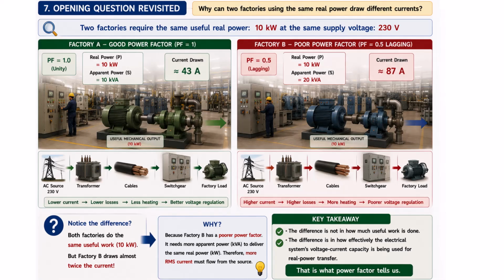Now return to the mystery from the beginning. Two factories require the same useful real power. Why can one factory draw much more current than the other? Because the factory with poor power factor requires a larger apparent power for the same real power demand. Therefore, its source, transformer, cables and switchgear must carry more RMS current. The difference is not necessarily in how much useful work is being done. The difference is in how effectively the electrical system's voltage current capacity is being used for real power transfer. That is what power factor tells us. Remember the physics, not just the formula.